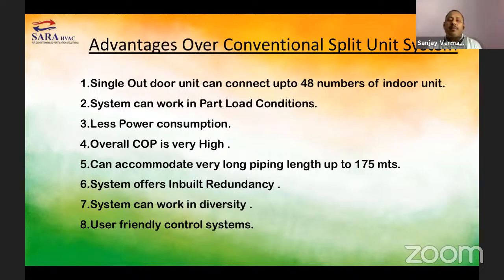The system can work in part load condition. For example, in a bungalow we have installed the VRF system. What will happen? We have one outdoor machine consisting of maybe 5 units above on the first floor area and 5 units at ground floor area, serving some bedrooms, halls, some dining areas. If you are using only the ground floor area, your power consumption will be based on only the ground floor area, not for the first floor area. So this system works on part load condition, not for 100%.